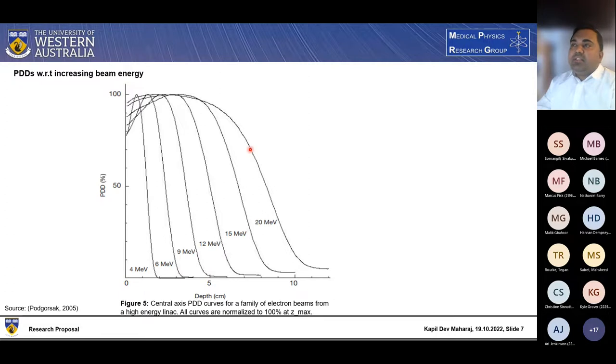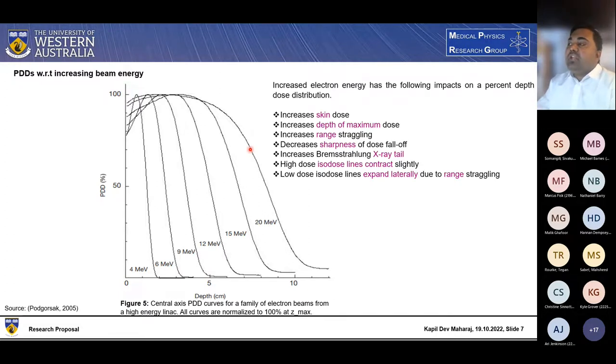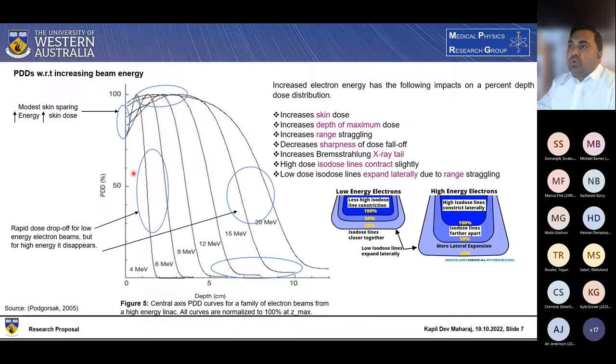So percentage depth dose with respect to increasing beam energy. Increasing electron energy has the following impact on percentage depth dose. Number one is increases the skin dose. So as energy increases, the electron skin surface dose also gets increased. Increased depth for maximum dose. Increased range of straggling as you can see in this figure. Decreased sharpness. For low electron energy, you can see the sharp drop of electron beam. However, for the higher energy beam, this sharpness becomes disappear. Increasing Bremsstrahlung x-rays is also because of the penetration, more penetration, more photons will appear which cause the more Bremsstrahlung x-ray tail with increasing electron energy. High dose isodose line contracts slightly. Low dose isodose line expands laterally due to range straggling as you can see in this picture.